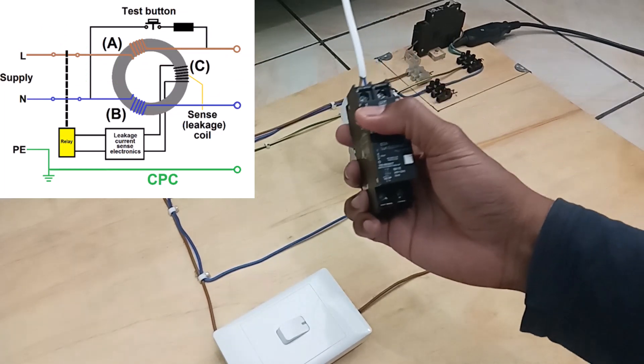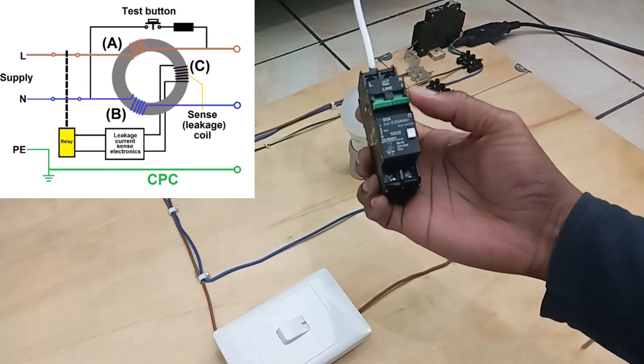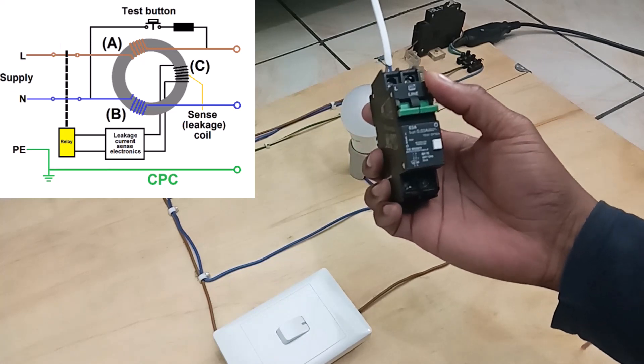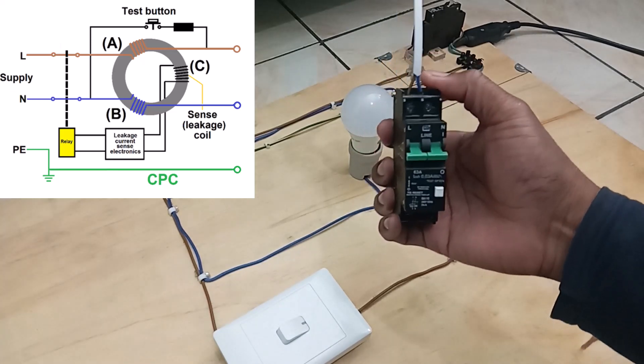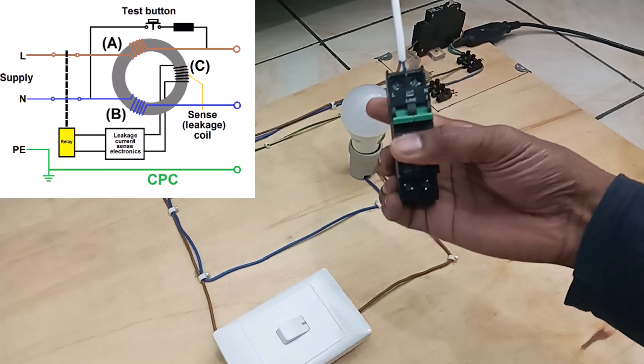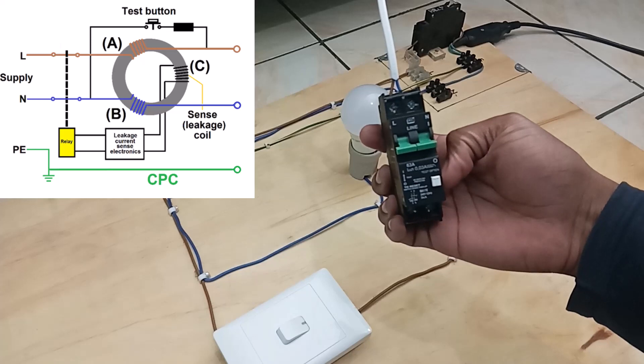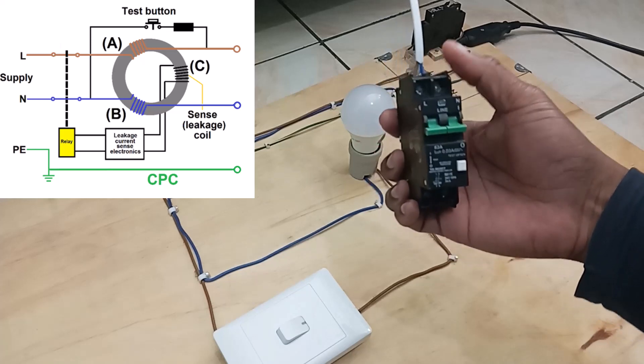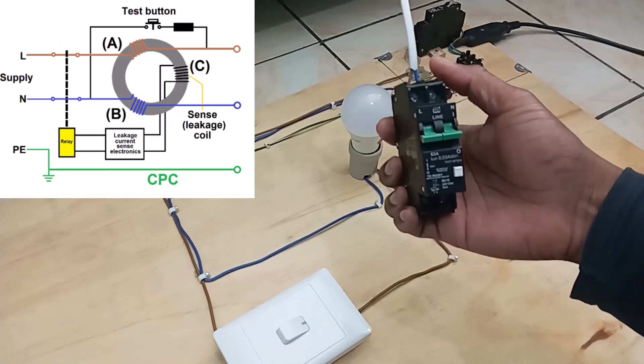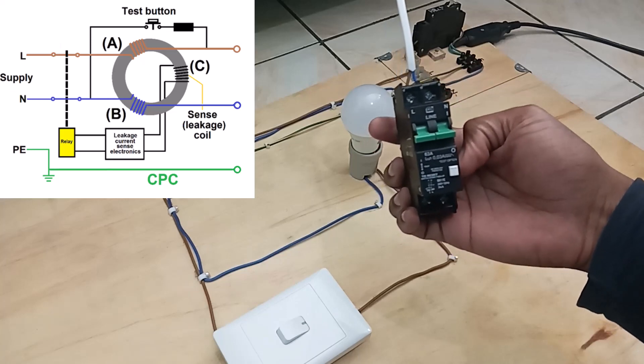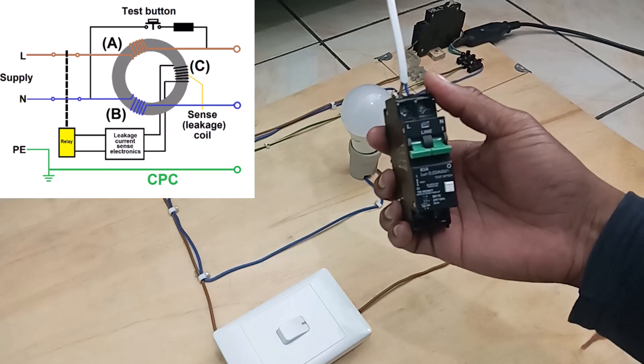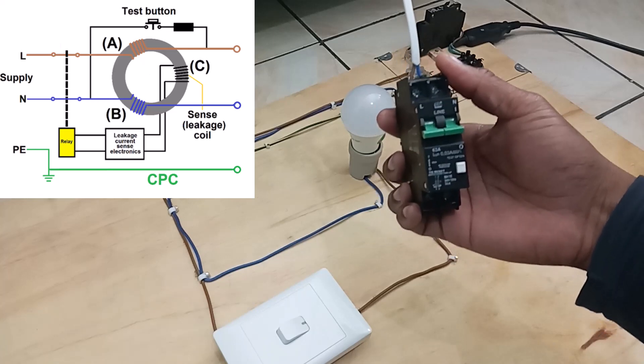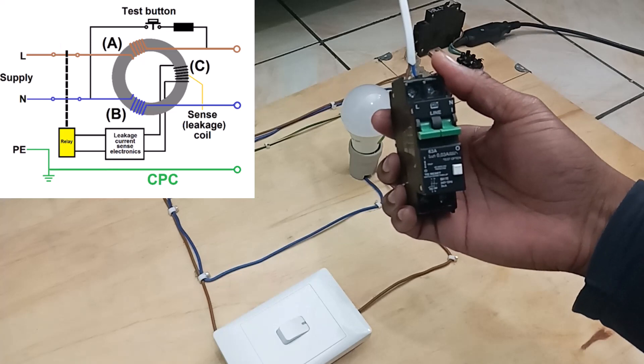So now this clever equipment here will be able to measure the current flowing into your live wire and then compare it with the current flowing out on the neutral wire. So if the current on the live wire is not equal to the current on the neutral wire, then basically it tells you, well, there have been a leakage current because the current that went in is not the same current that's coming out.